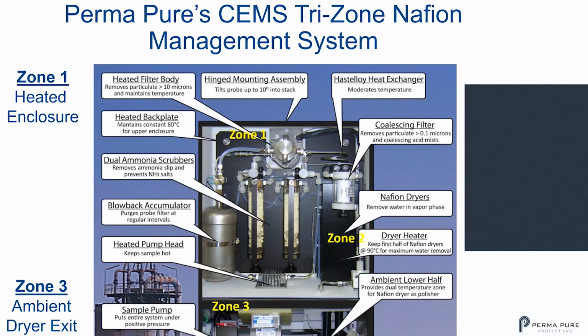From here, the sample gas goes through this Hastelloy heat exchanger into the coalescing filter. The coalescing filter and this entire area is heated to roughly 80 degrees C to 90 degrees C, depending on the system. That keeps the sample in the vapor phase. At the same time, 80 or 90 degrees C is low enough to condense out the acid mists. So here we're getting rid of the acid mists, and also all the particulate over 0.1 microns.